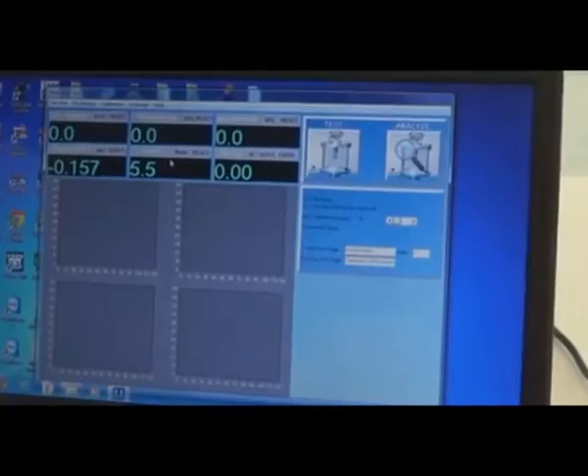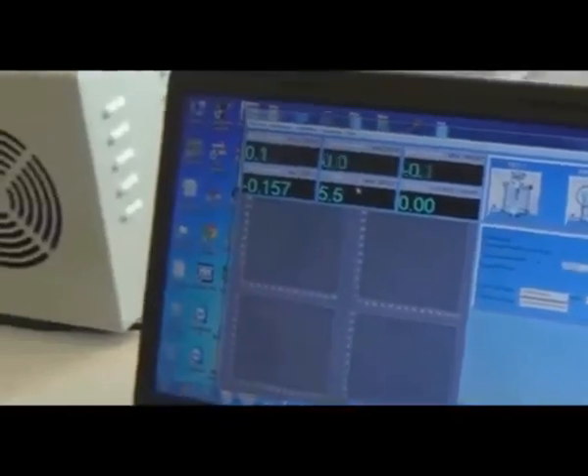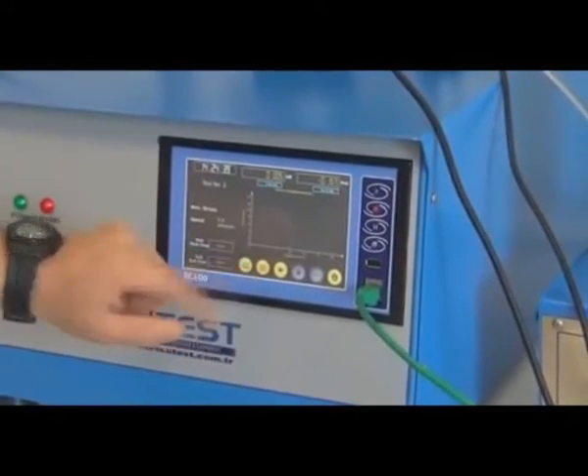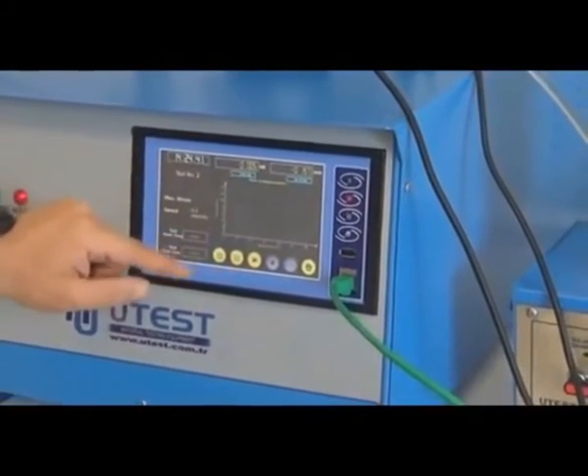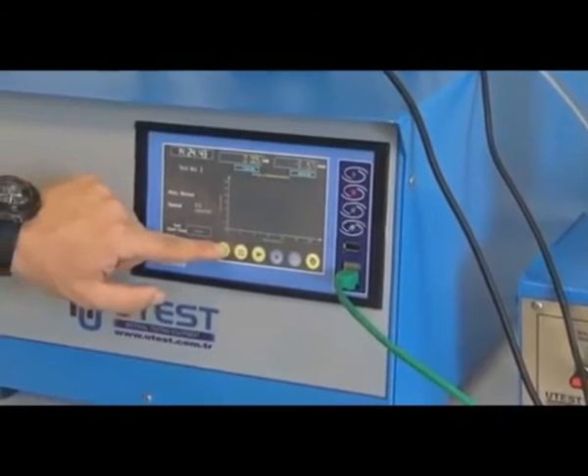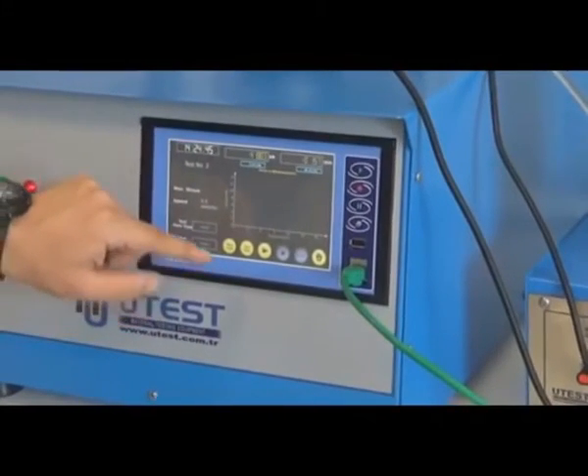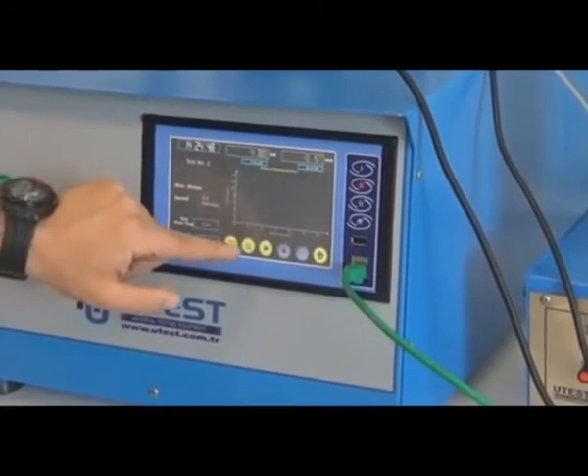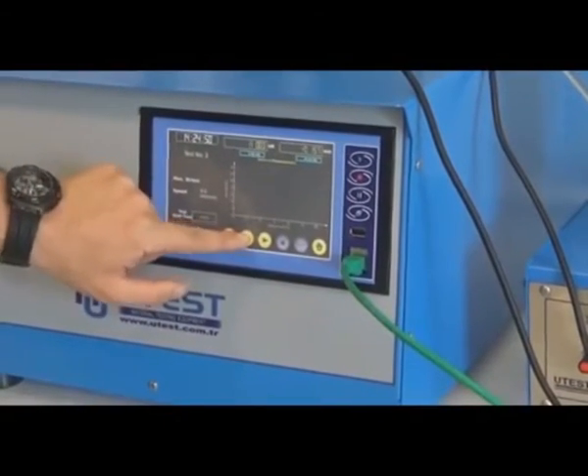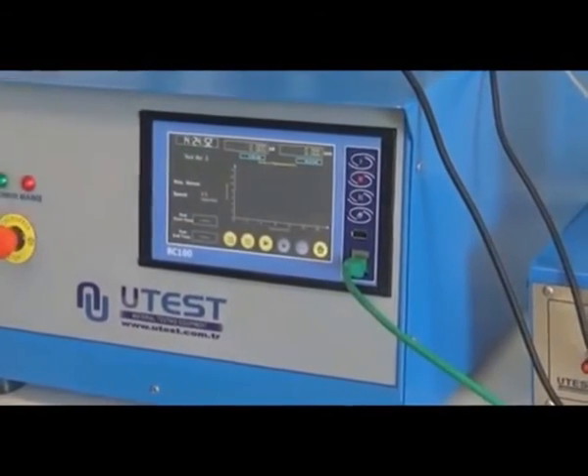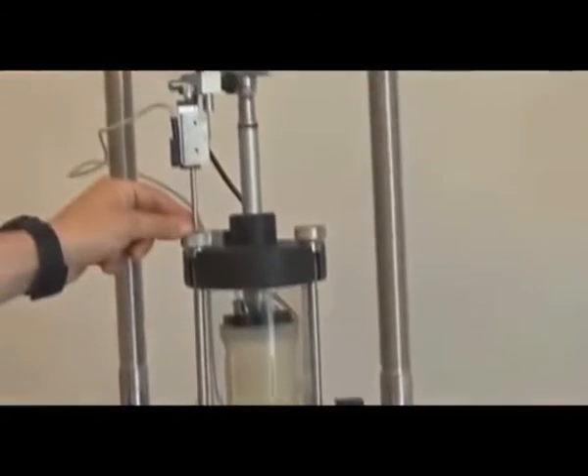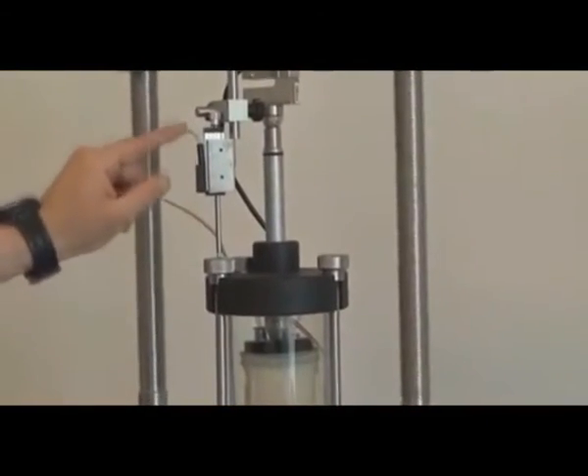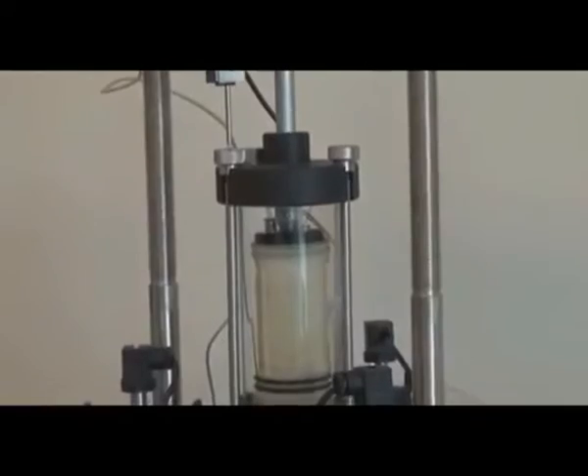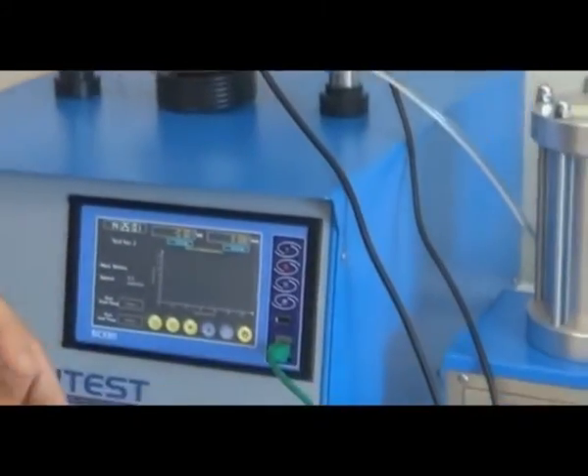The axial displacement and the force are going to be reset on the TFT screen here. There are two buttons on the test screen. One of them is tare load, which resets the load, and the other is tare displacement, which resets the displacement, I mean the LVDT reading values over here. Now they are all set to 0, and we are ready to start the test.